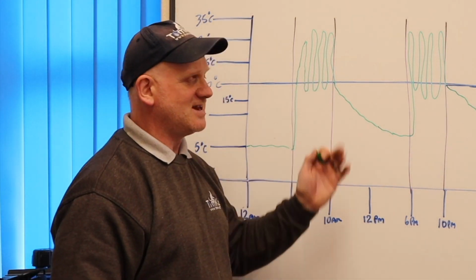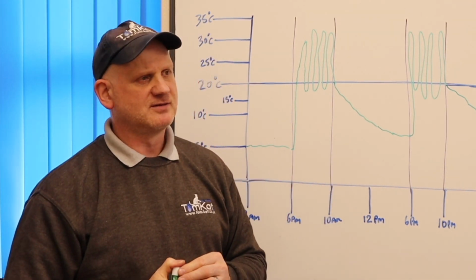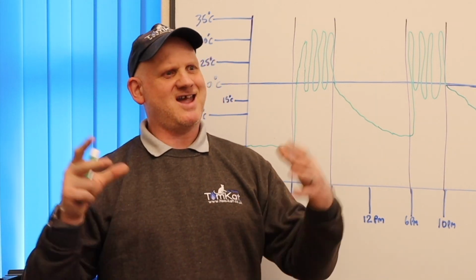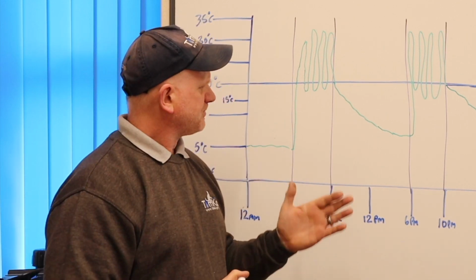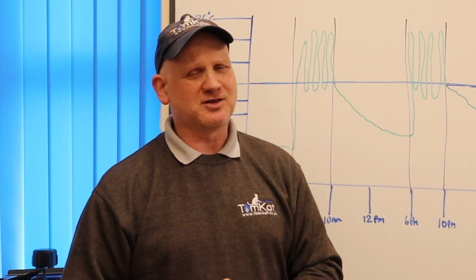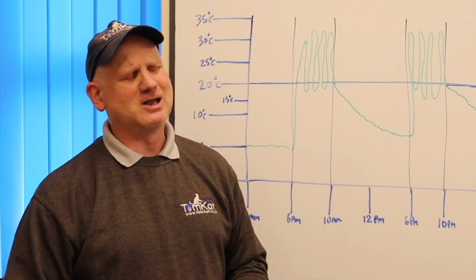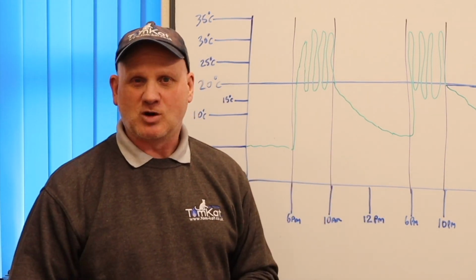Now, massively wasting energy because the room stat only knows when to turn on and off. It doesn't know what the temperature of the rooms are, and because you've got the boiler set at 82 degrees, the boiler doesn't know. It's just going to give you the full kilowatts. Now, the average kilowatts in a property in the UK is about 8 kilowatts, and if you've got a boiler what's doing 30 kilowatts on heating, it's going to massively overshoot. So you're wasting loads of energy, even though you've got a time clock and you've got a room stat. This is slightly exaggerated, but that's what can happen.